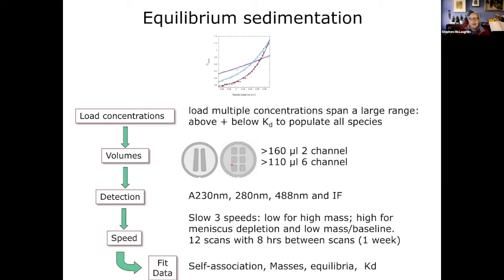For equilibrium experiments, typically use a six-sector cell taking 110 µL per channel at different concentrations spanning above and below the Kd to populate all species. Run at three speeds: low for high-mass species, high for depletion of the meniscus, and an intermediate speed. Typically collect 12 scans with eight or more hours between scans, confirm equilibrium at each speed before moving on, then fit the data to get ideas about self-association masses and equilibrium constants.